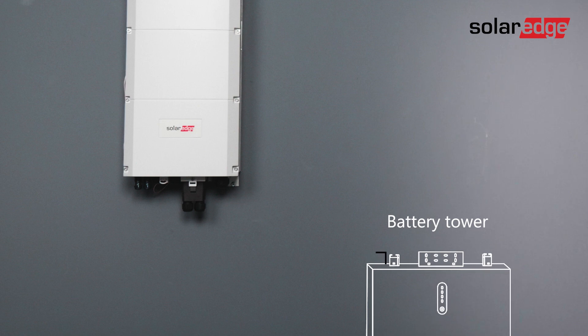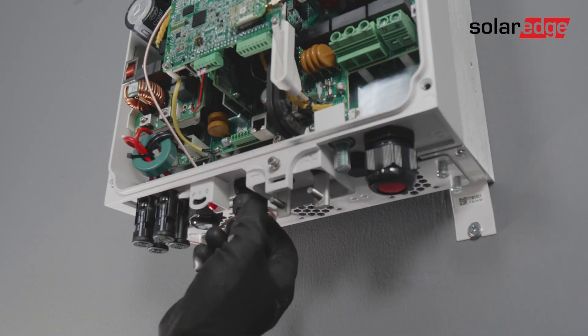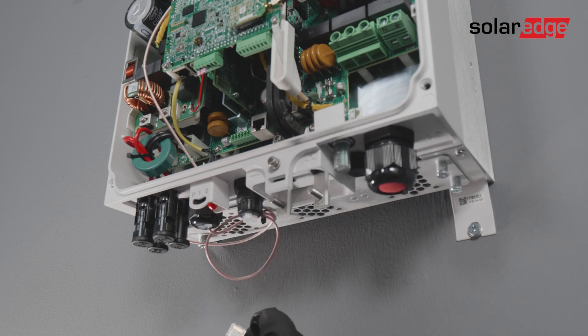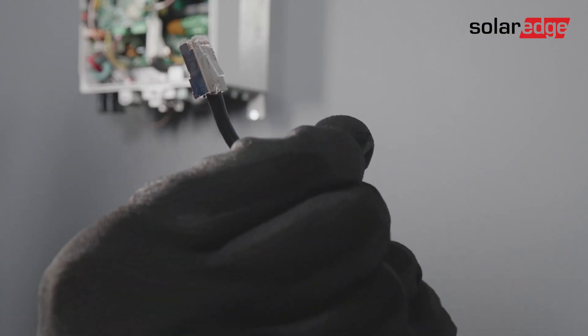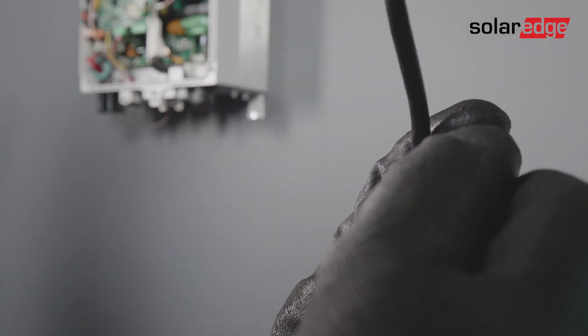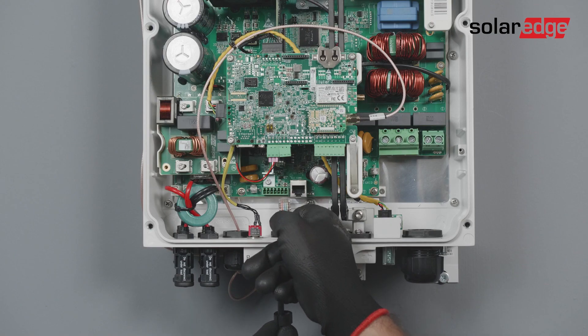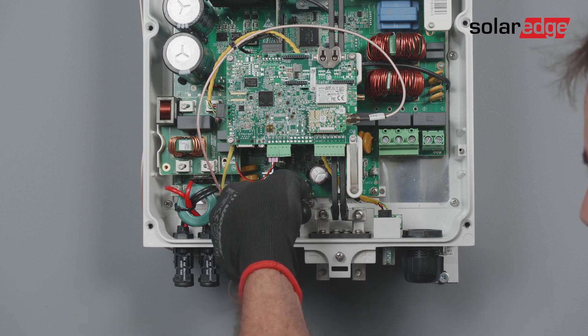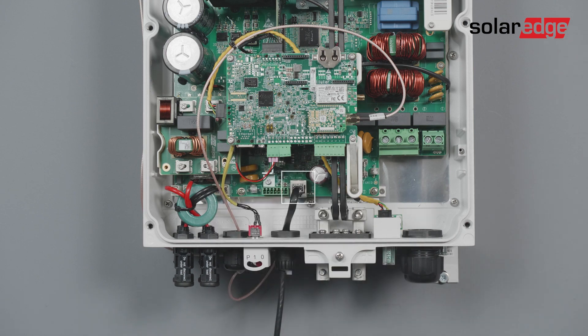First, let's connect the communication cable between the battery and the inverter. This is established using the CAN-BUS protocol. Open the communication gland 2 and pass the CAN-BUS connector and cable through the gland. Please note the cable size and the gland pass-through. Connect the cable to the CAN-BUS connector located close to the gland.